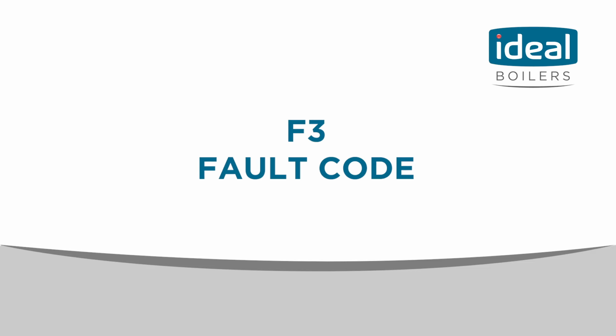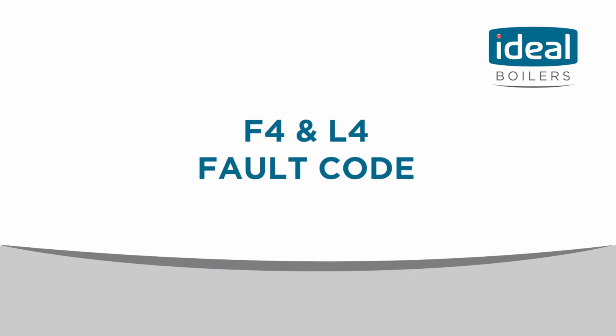If you encounter an F3 fault code, it indicates a fan error. Press the restart button. If the fault reoccurs, contact Ideal Boilers. If you encounter an F4 or an L4, it indicates a flow thermistor fault. Try a restart. If the fault reoccurs, contact Ideal Boilers.